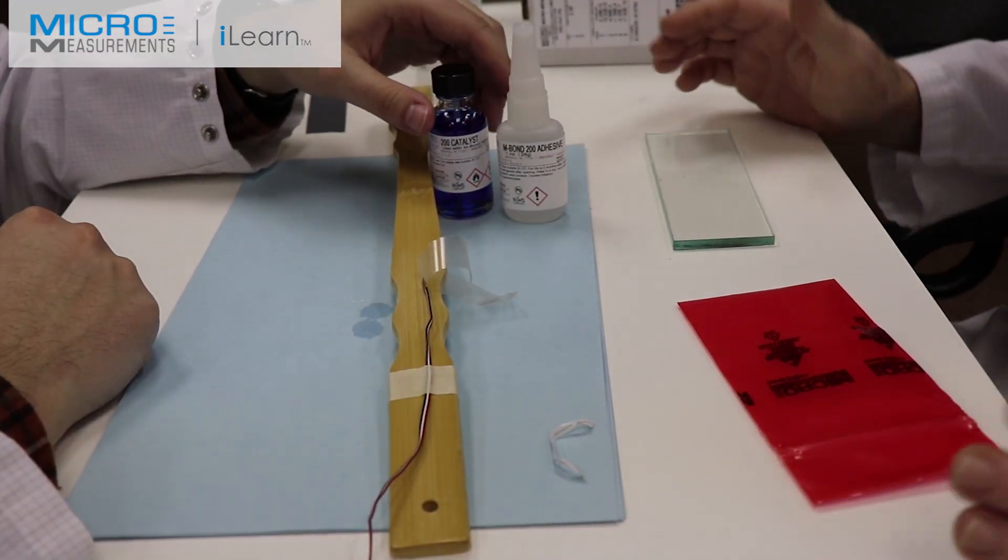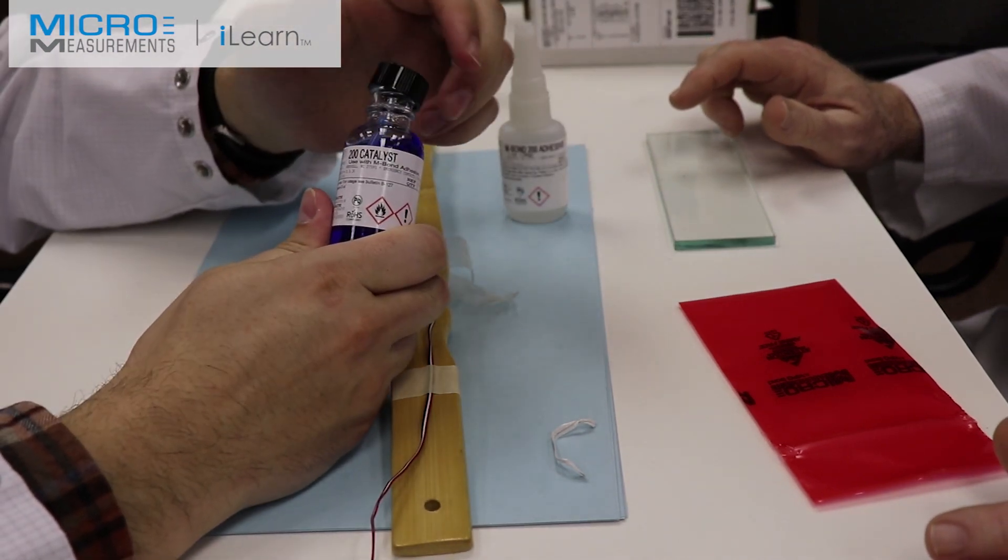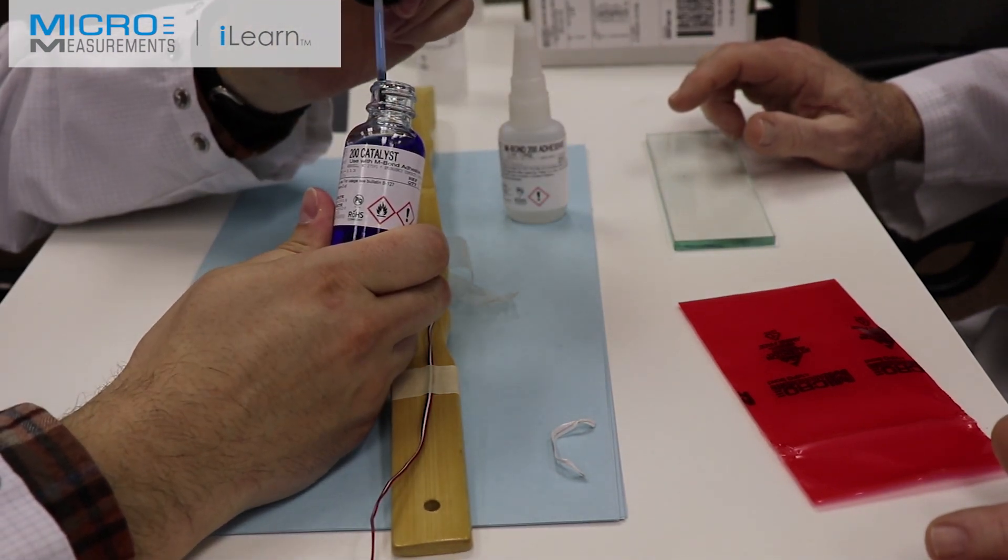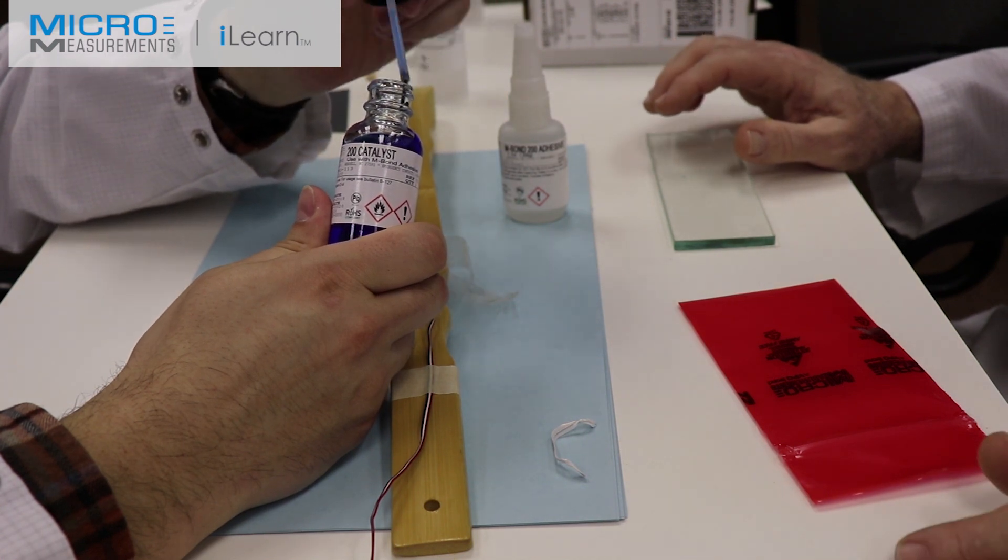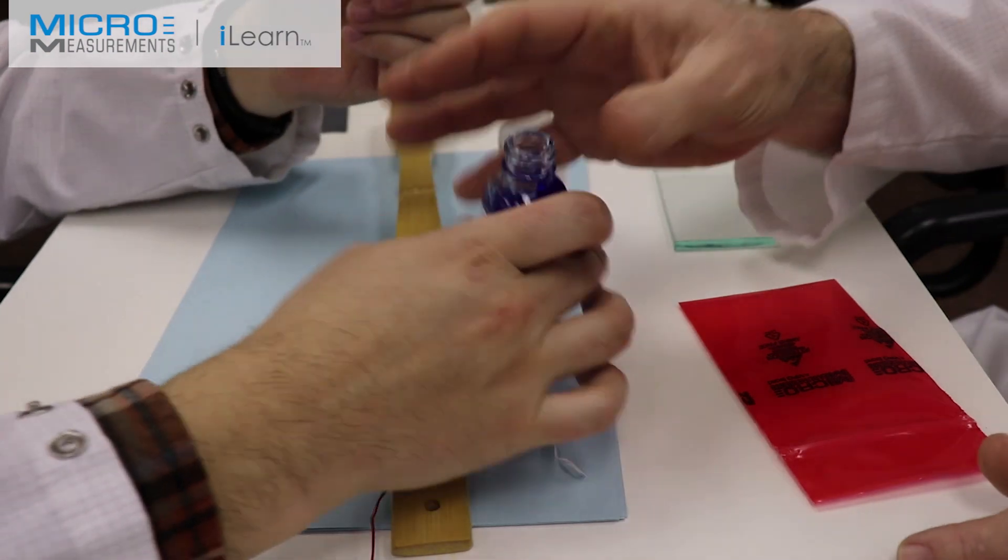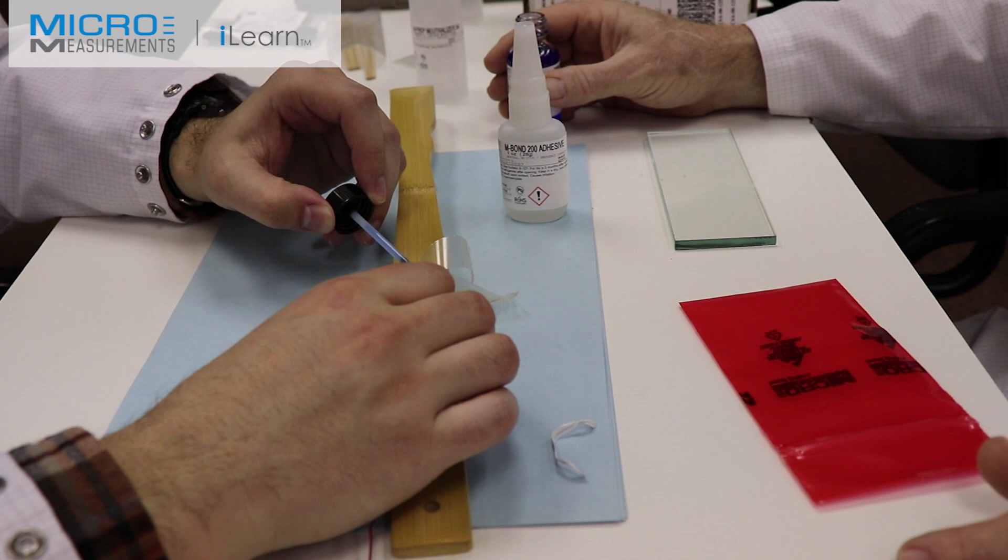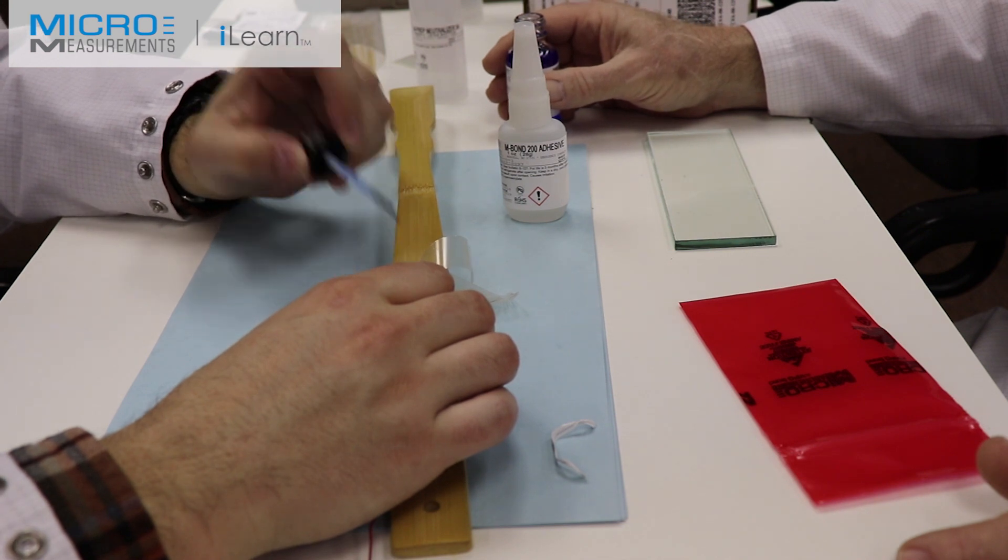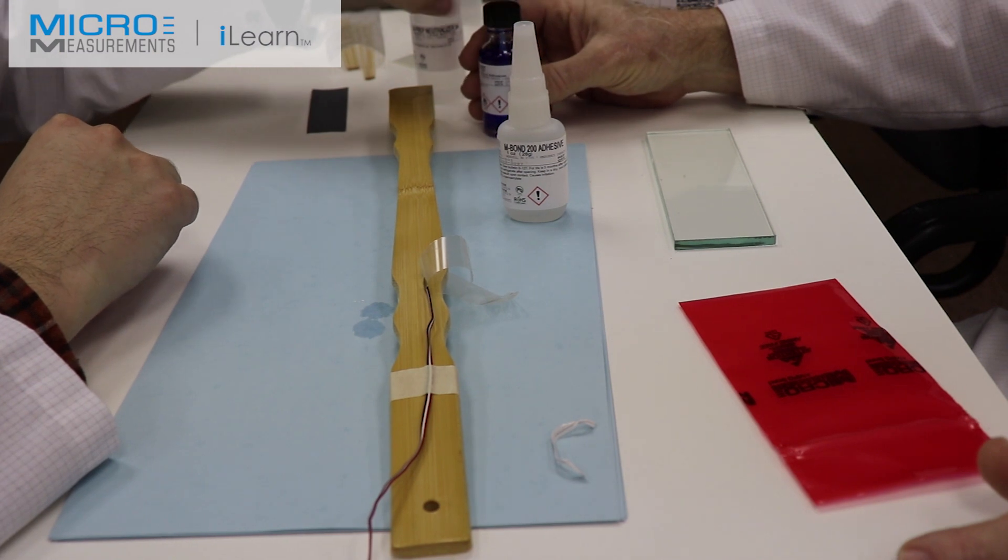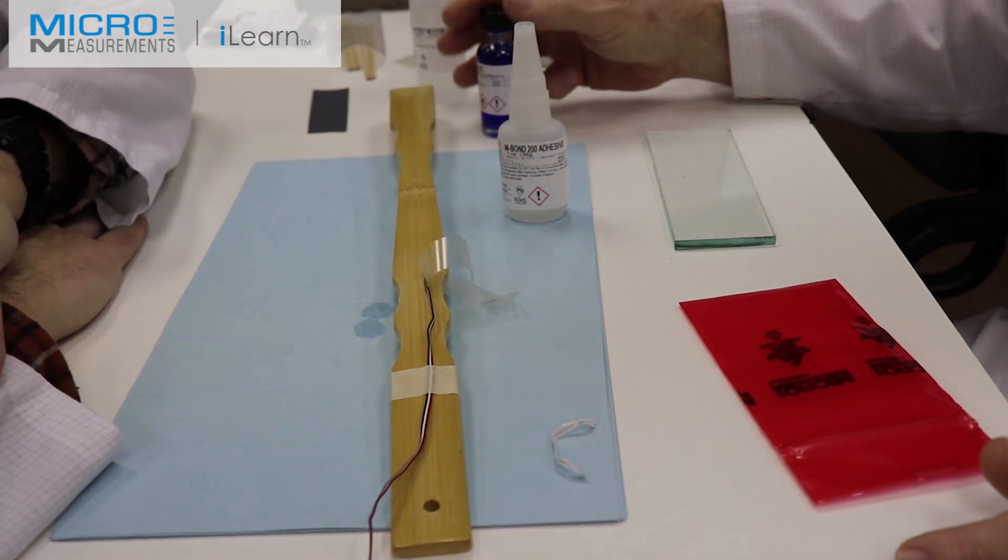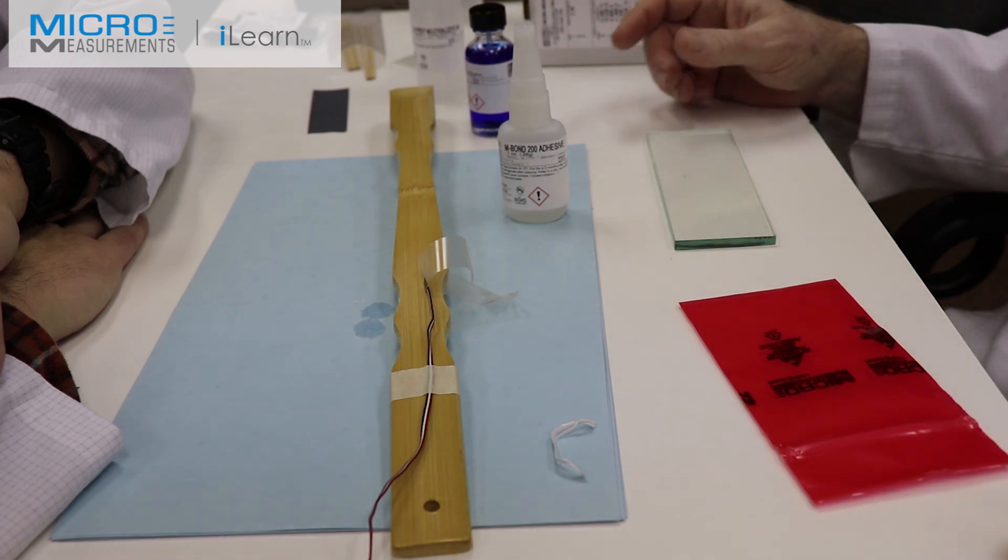Now that we've got our gauge positioned and surface preparation is complete, we're going to put on our catalyst C. On the inside of the neck of the bottle, Colin's going to hit it eight to ten times, removing almost all the liquid material. Then with a squeegee motion, he's going to squeegee across to wet the gauge. Now we wait one minute of air dry time for the catalyst C so the solvents have an opportunity to escape.